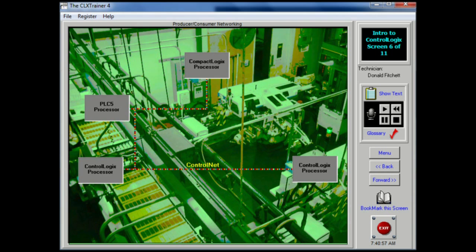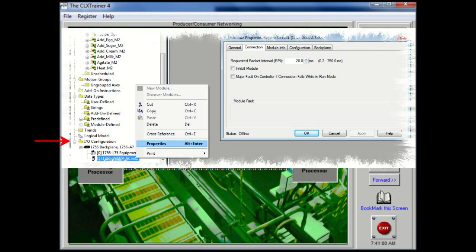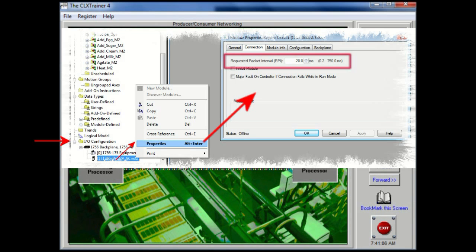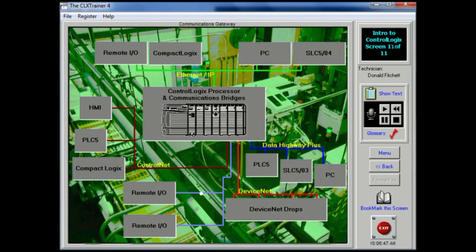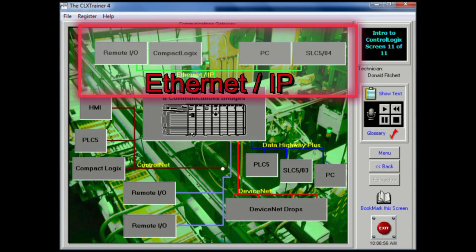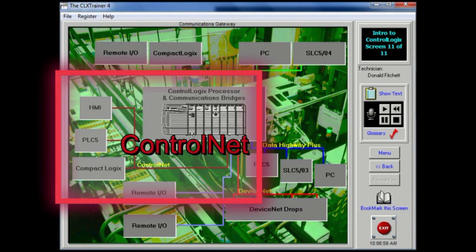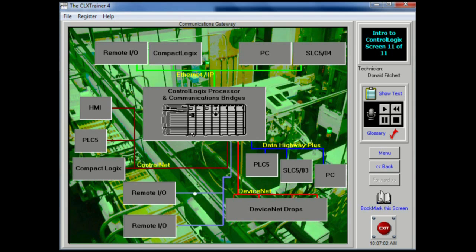This networking model allows individual modules to produce data without having been polled by a controller first. Data will be multicast based on either a time interval or a change of state. The modules for ControlLogix systems — including controllers, communications, and motion modules — are flash upgradeable, enabling users to perform flash memory upgrades to the firmware of any module. The ControlLogix system can also function as a communications gateway, containing modules needed to communicate with other networks such as Remote IO, Ethernet IP, Data Highway Plus, and ControlNet, allowing messages to be sent to and from those networks.